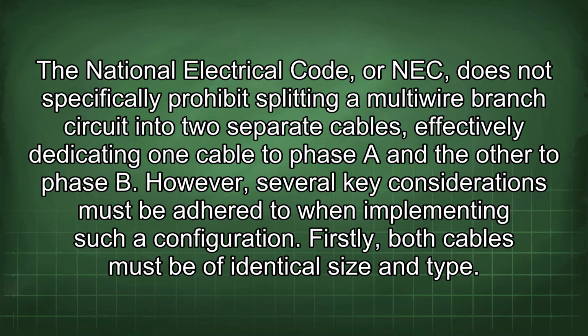The National Electrical Code, or NEC, does not specifically prohibit splitting a multi-wire branch circuit into two separate cables, effectively dedicating one cable to phase A and the other to phase B. However, several key considerations must be adhered to when implementing such a configuration.